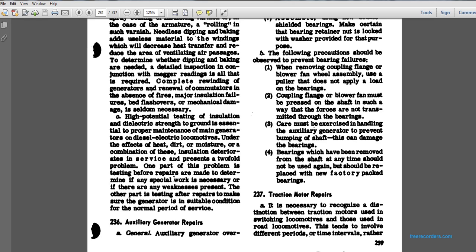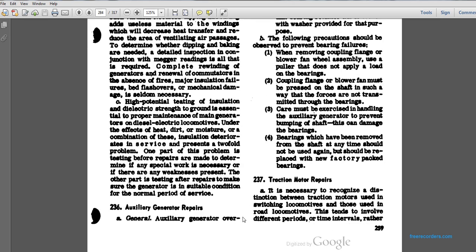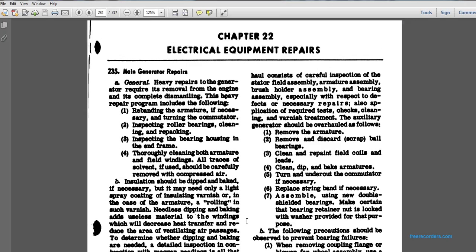236. The auxiliary generator repairs. Generally, an auxiliary generator overhaul consists of careful inspection of the stator field assembly, armature assembly, the brush holder assembly, and bearing assembly, especially with respect to wear and necessary repairs. Also required are testing, checks, cleaning, varnishing, and treating. An auxiliary generator should be overhauled as follows: remove the armature, discard or scrap ball bearings, clean, repaint field coils and leads, clean, dip, and bake armatures, turn and undercut the commutator if necessary. Replace a string band if necessary.